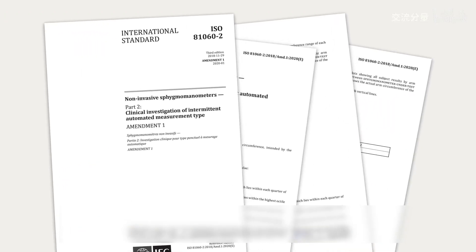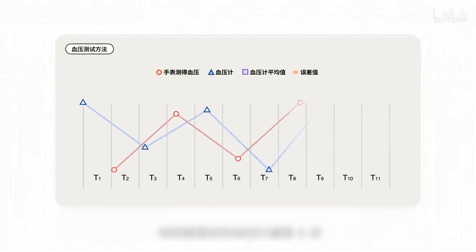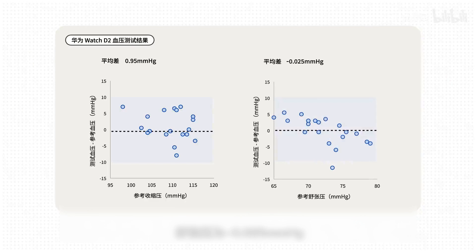We designed this experiment according to international general standards. The reference device is the Omron HEM-7361 electronic blood pressure monitor. The test method is: after the subject rests quietly for 10 minutes, measure continuously and alternately on the same side of the arm. Each group of measurements uses the blood pressure monitor six times and the watch five times, with each measurement spaced more than 60 seconds apart. The test value of the watch is compared with the average value of the reference values of the two blood pressure monitors before and after. Each watch is tested for a total of four groups of 20 values, then data analysis is performed. The average error of the Huawei Watch D2 systolic pressure is 0.95 mmHg and the diastolic pressure is -0.025 mmHg.